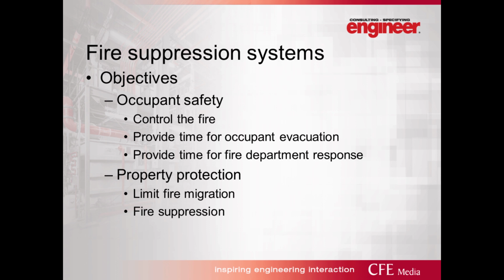So from an overall perspective, what are we trying to achieve with fire suppression systems? What are the objectives? In general, there are two. The first one is occupant safety. This is paramount. The most critical objective for a fire suppression system is to provide occupant safety first. And that means controlling the fire. A lot of times there's a misnomer or a misconception that fire suppression systems always suppress a fire and extinguish it. That's not necessarily the case, nor is that necessarily the proper design application for all the different types of hazards that we may encounter.